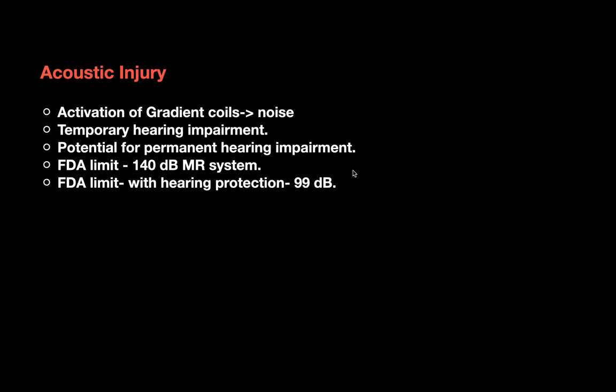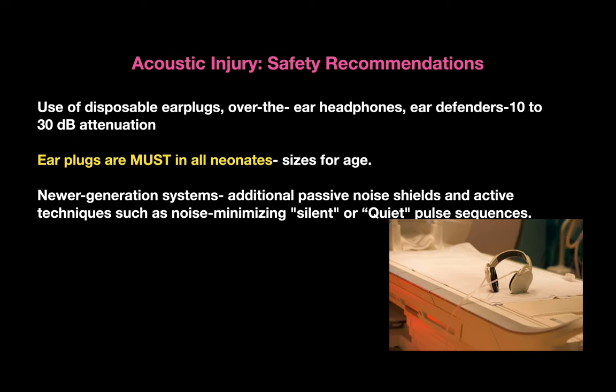The FDA limit for noise without hearing protection is up to 140 decibels, and with hearing protection up to 99 decibels. Safety recommendations for acoustic injury include disposable earplugs, over-the-ear headphones, and ear defenders which can attenuate 10 to 30 decibels of sound. Earplugs are must for all neonates, with different sizes available. Additional passive noise shielding and active techniques such as noise-minimizing or silent pulse sequences can also be used.